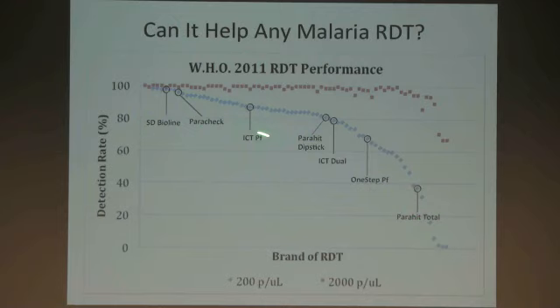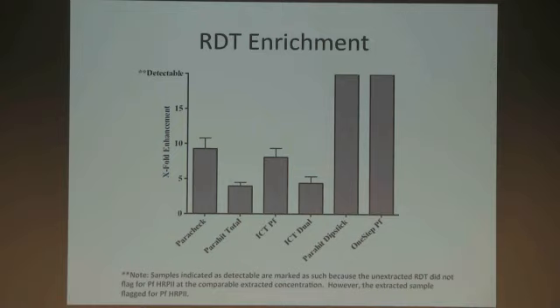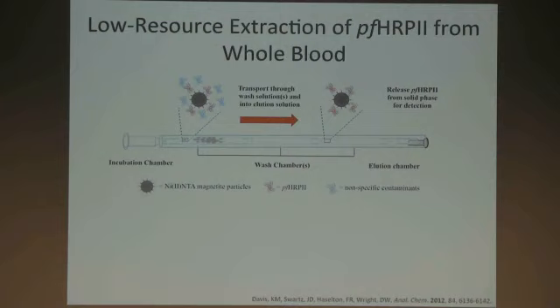We also asked: could we make the bad kits into good kits? We took even the worst kits — ones that were not detectable — and turned them into incredible results. We get between five and ten times enhancement for kits that work well, and we can take kits that don't work and make them work at the WHO threshold. We can salvage even the worst test kit, one where maybe some of the antibody isn't active, has been degraded, or used poor manufacturing processes, and make it work.